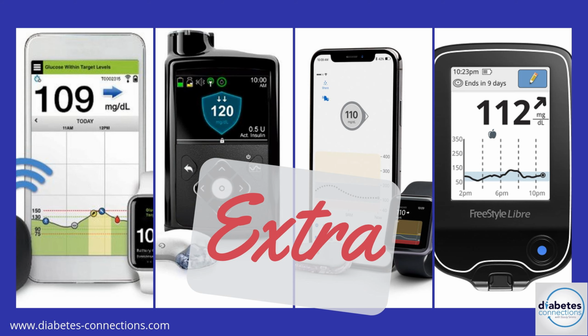So the critical aspects of this, number one, is putting the settings in properly, and number two, responding properly. So I'll talk about the settings first. Because of the lag time, it's not reasonable to put the low alert at 70. If the sensor thinks you've gone below 70 and your blood sugar is falling, you're probably around 50 already. So it's necessary to put the low alert for most people somewhere between 80 and 90, just to be able to catch it while it's still treatable and you may still be able to prevent the low.